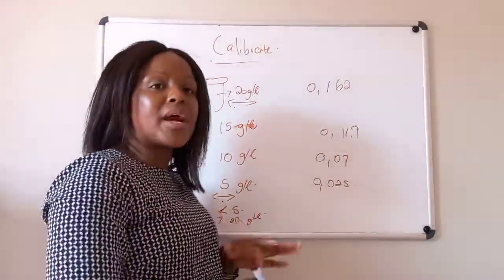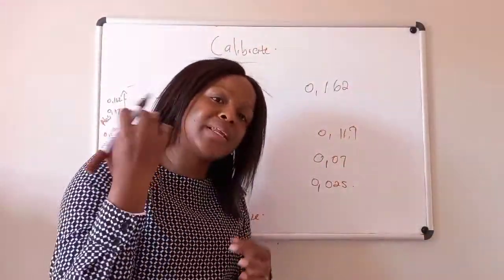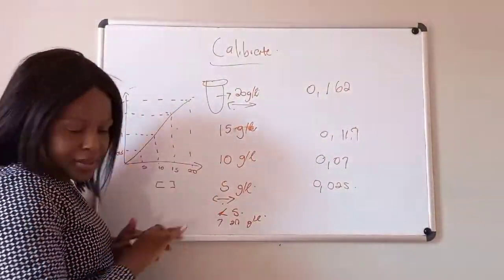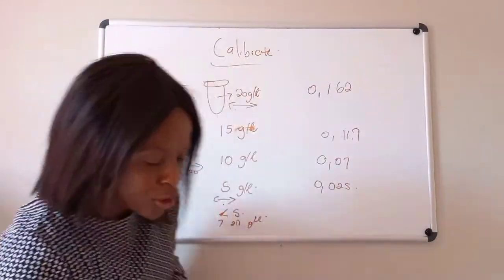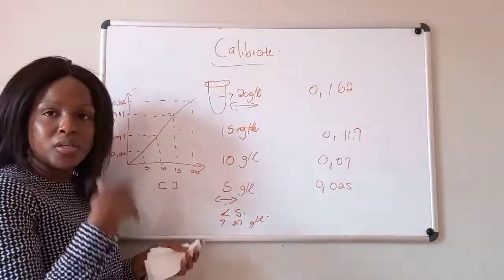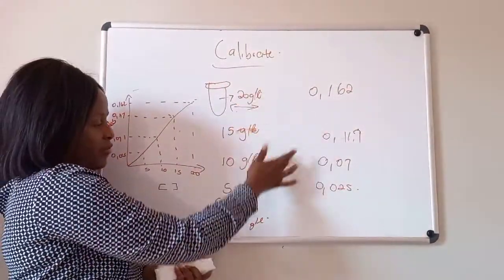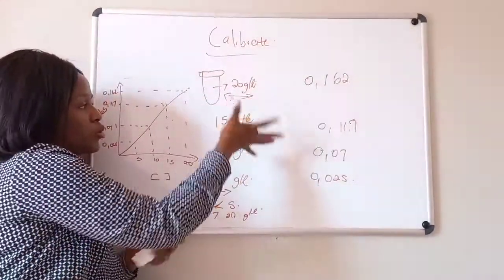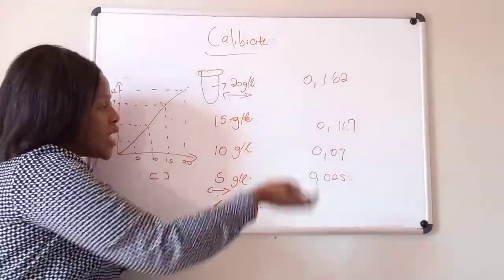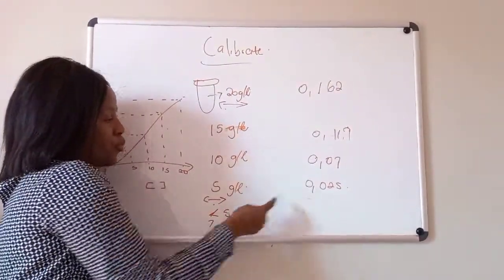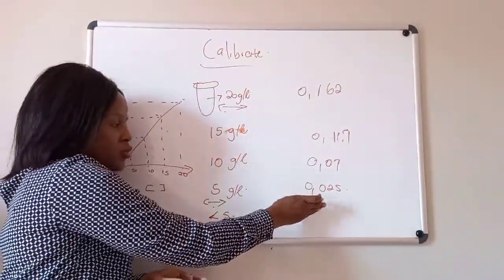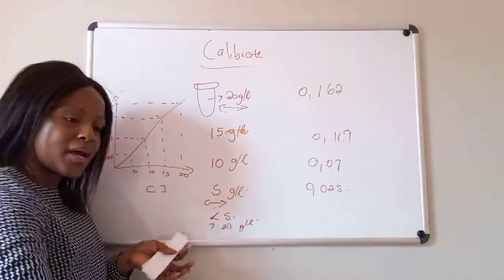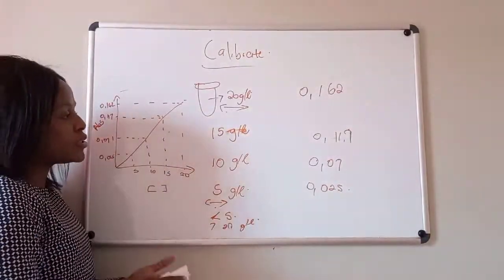Because another thing with calibration, basically you are determining the accuracy of the instrument as well when you calibrate. So this is what the instrument usually would do. You're going to have those calibrators, or it will do its dilutions depending on whether it had only 1 standard or 4 standards. And then from those 4 standards, they will have the concentration as well as the absorption value for all of them. And then when they run, the instrument will just plot a graph.